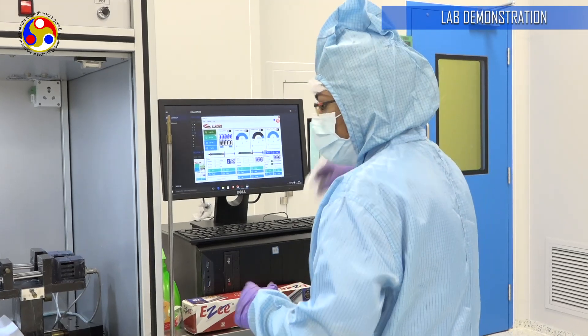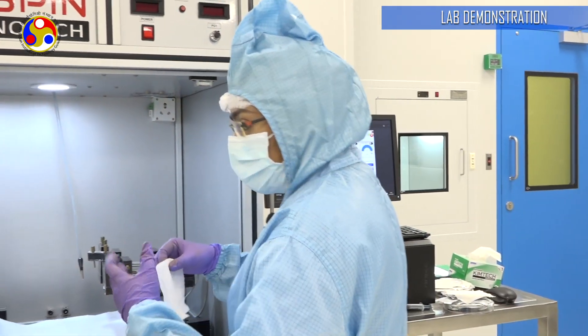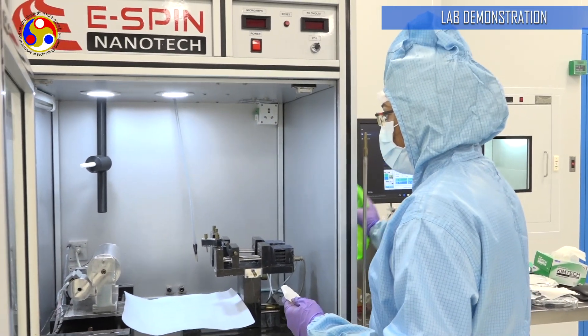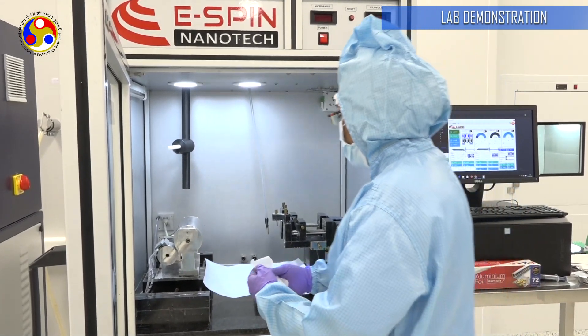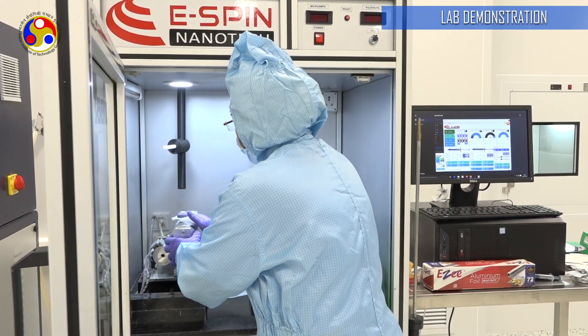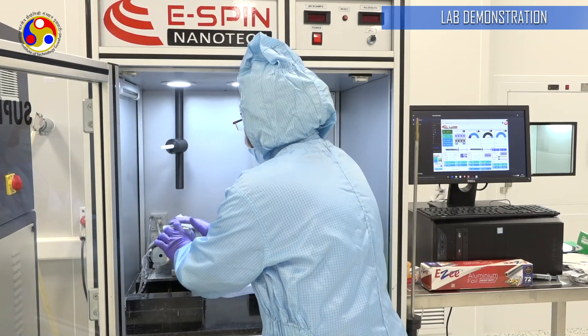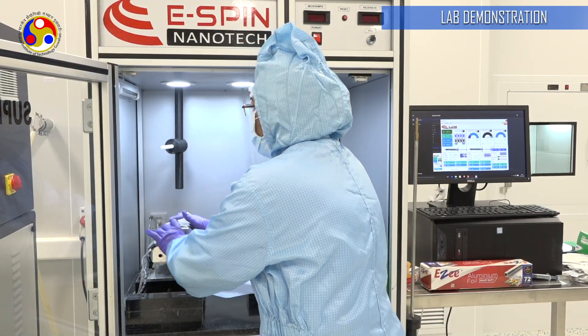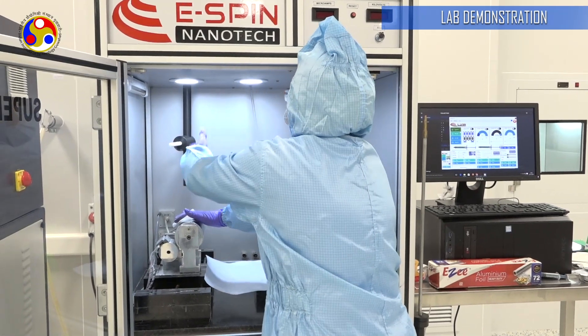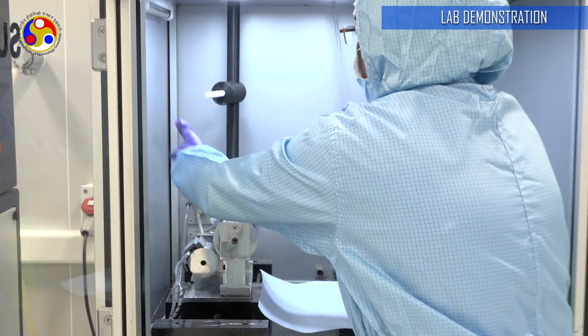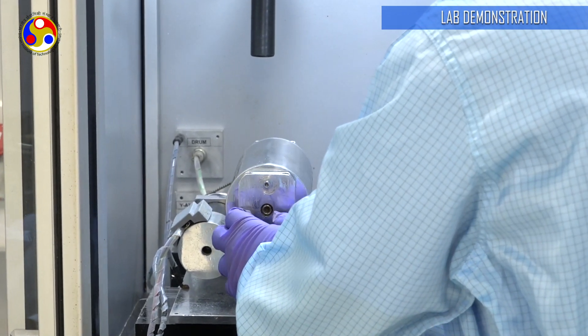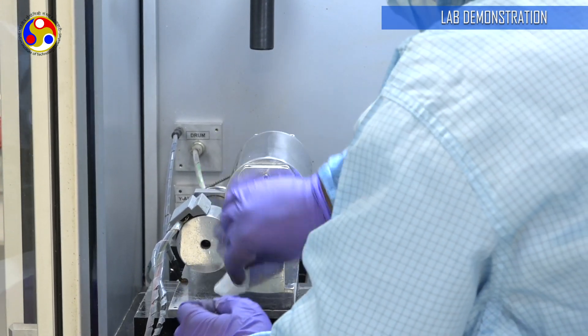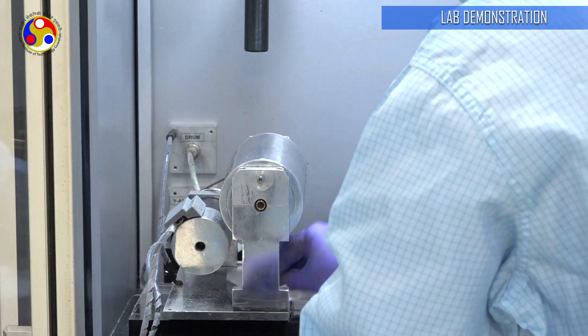The final step is to clean the machine after use. Because we typically apply a high voltage between the collector and the source, because of the strength of the electric field, a lot of fibers get deposited inside the chamber everywhere, in the ceiling, in the sides. It's important to keep the machine clean after use so that no contamination can occur in the future.